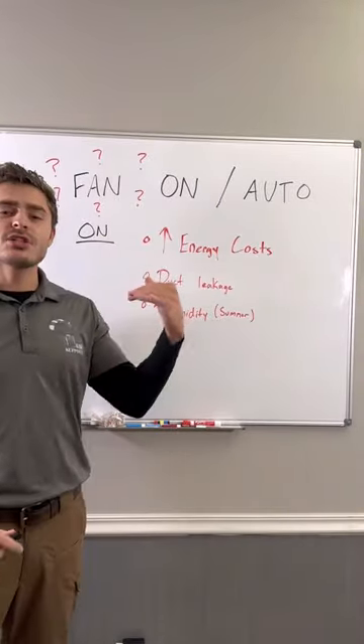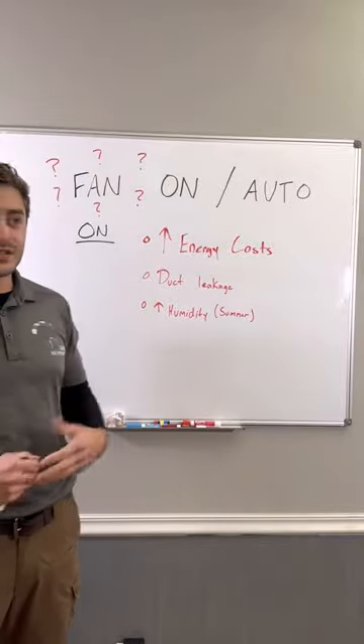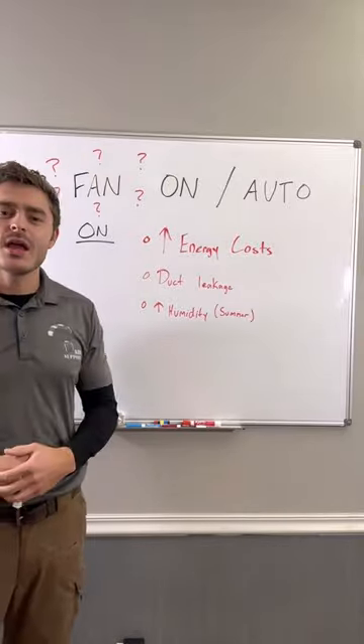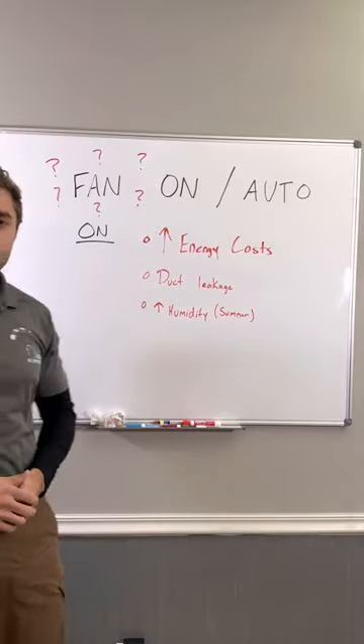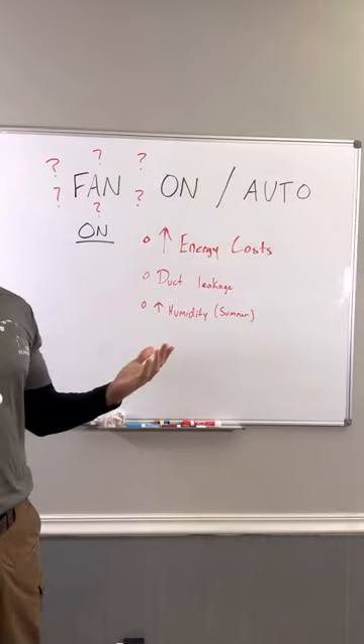There are a few reasons you might not want to use the fan on feature. You have increased energy costs. Essentially, older equipment, especially anything before 2015-2018 that era, has an older style blower motor. It costs a little bit more money. You're talking maybe 10-20 bucks a month difference on utility bill. Nowadays with our more efficient motors, it's pretty marginal. You're not going to really see that.